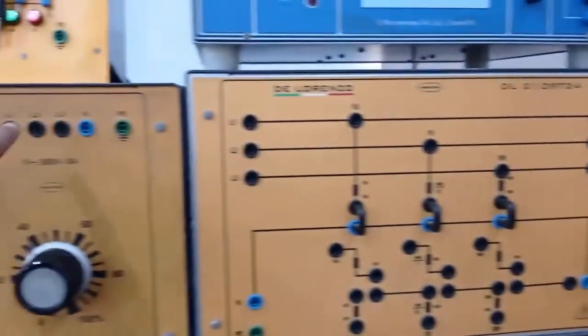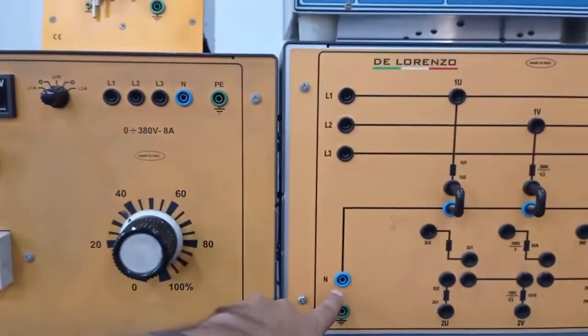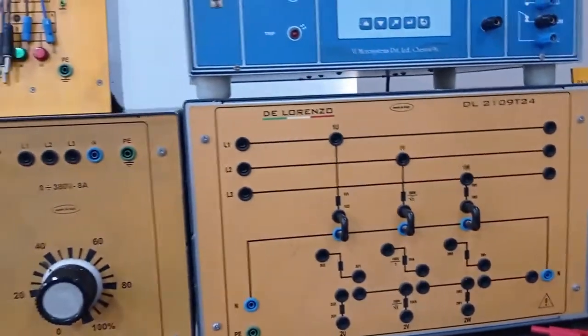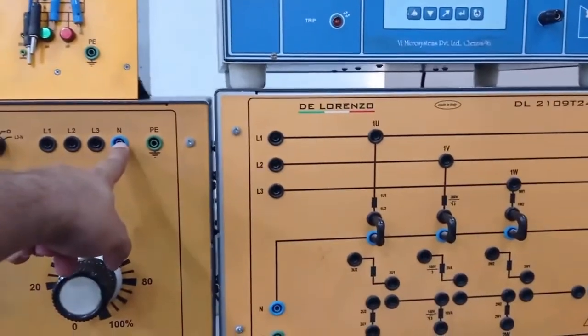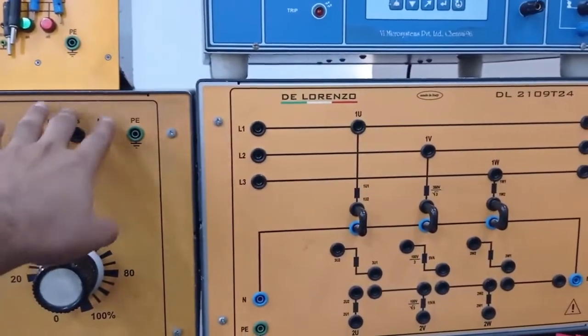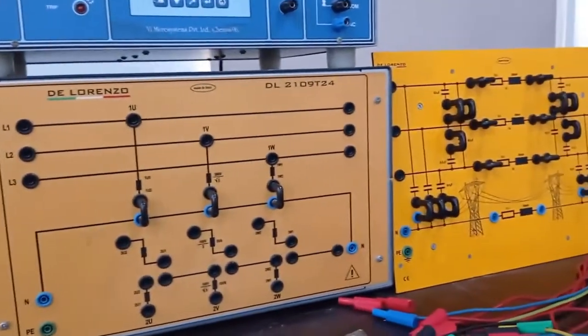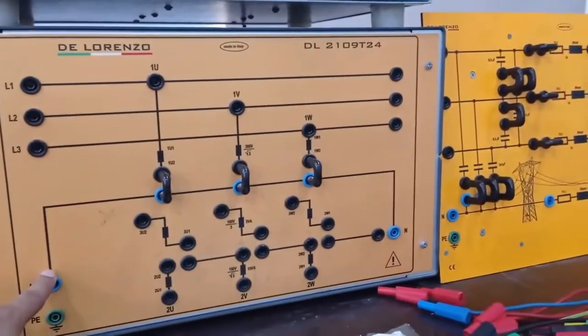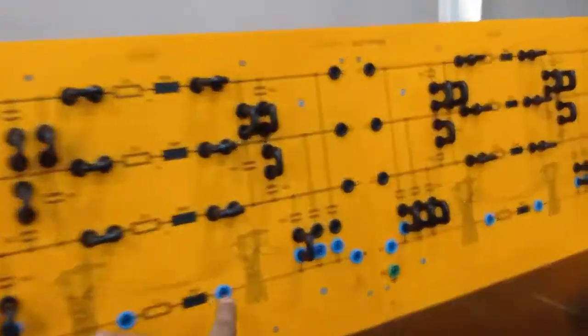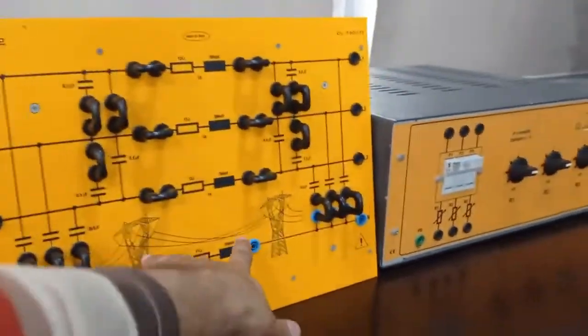Make sure that the neutral of the source is not connected with this neutral, because we are going to treat this neutral as ground. So this is an ungrounded system, and that's why we keep this neutral away. This neutral will remain isolated from the rest of the circuit. So this N neutral will be treated as ground onward. Make sure that these grounding resistances have been short circuited.